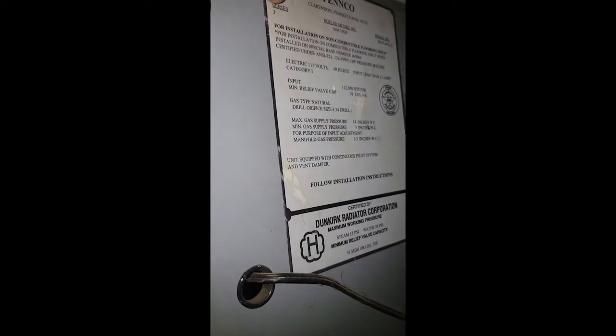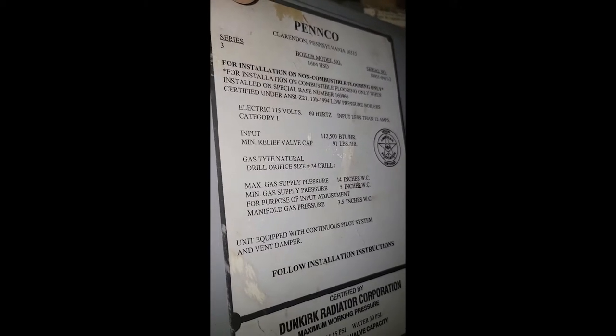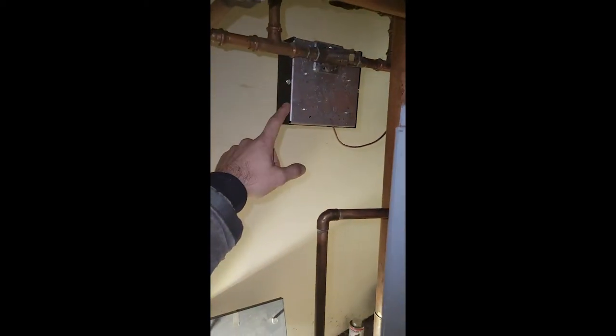This is a Pennco cast iron natural gas boiler, model number 1604 HSD Series 3. We have an automatic water feeder on the boiler — it's 24 volts and has a low water cutoff. It is currently not on, so we know there is plenty of water in the boiler.